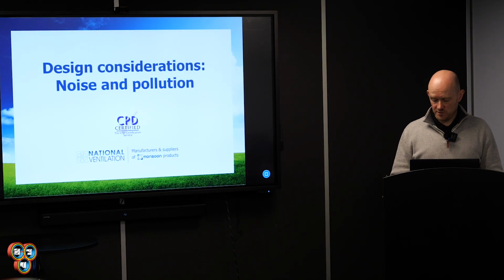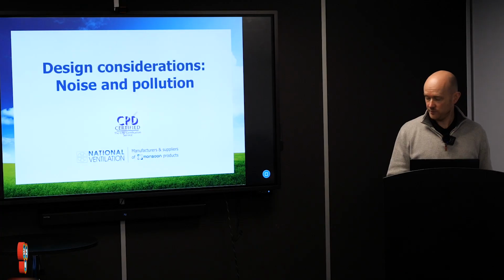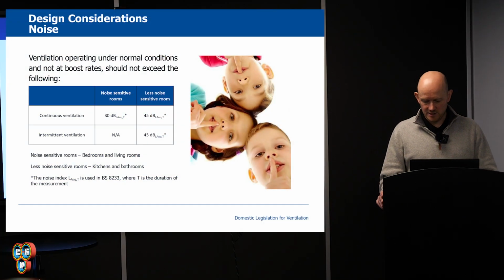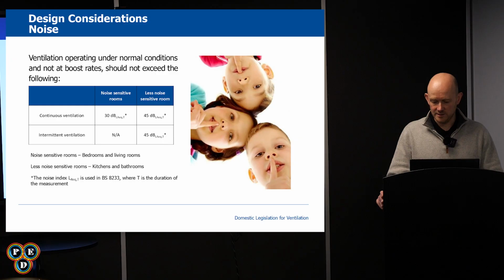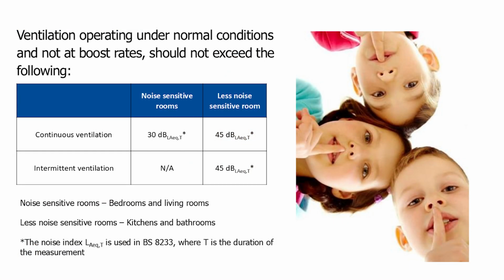So these are design considerations we're talking about now, about noise pollution. Noise is an important consideration that needs to be addressed, as noise pollution can be a concern within dwellings. Part F states certain noise levels should not be exceeded under nominal operating conditions, not boost rates. Noise should not exceed 30 decibels within bedrooms and living spaces and cannot exceed 45 decibels within kitchens and bathrooms. Trust me, if you were at 29 decibels in a bedroom after an MVHR installation, you would be getting a phone call from the homeowner. You'd be complying, but 29 decibels, even though it's within Part F, is very loud.